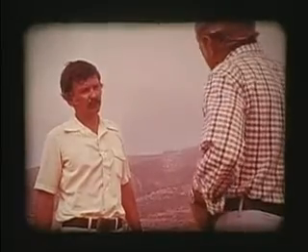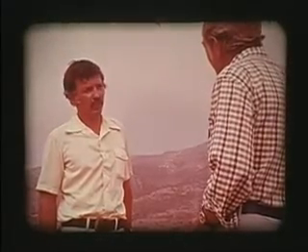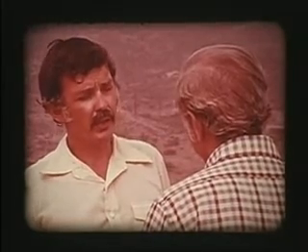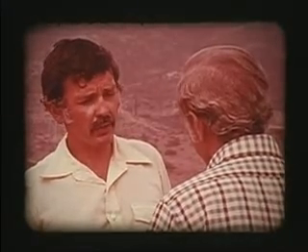The San Andreas Fault is nearby, isn't it? The San Andreas Fault is located about 60 miles over in this direction. If a giant earthquake were to occur on the San Andreas Fault, one larger than ever recorded, we could expect ground motion at San Onofre to reach a certain level of intensity. We doubled the calculated accelerations from the San Andreas Fault and then added a safety factor. And we finally provided the structural engineers with a considerable margin of safety to design to.